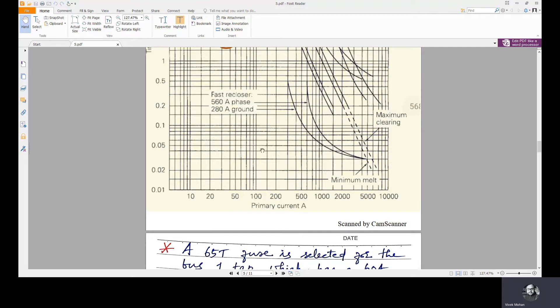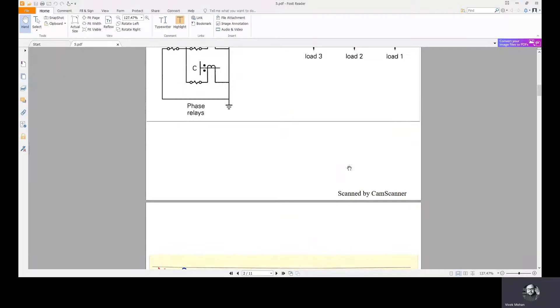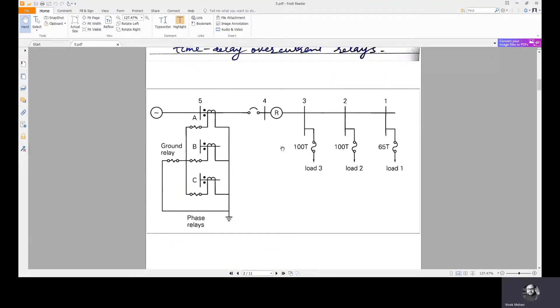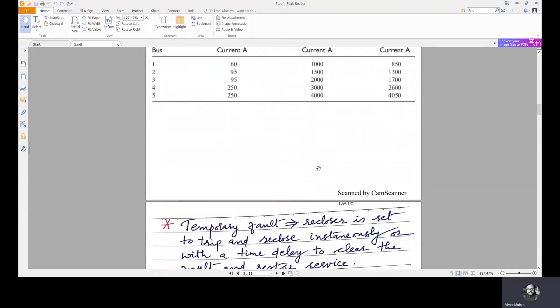After 0.05 seconds, the recloser opens, and then recloses after half a second because the first fast recloser time duration is half a second. If the temporary fault is self-cleared by the time it closes again, then it restores the service. The recloser restores service after the fast recloser itself. But if it's a permanent fault, that is what we are going to see in the second case.